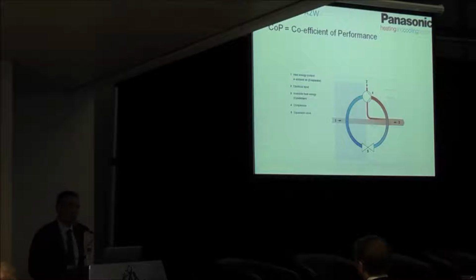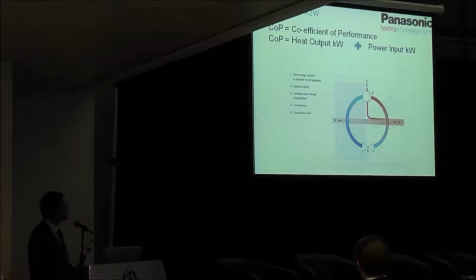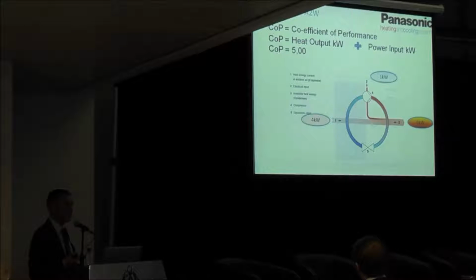So when we talk about air-to-water heat pumps, we hear the term COP, or coefficient of performance, quite a lot. What exactly is that? It's simply the heat output divided by the power input. So if we have a heat output from a heat pump unit of 5 kilowatts and a power input of 1 kilowatt into the compressor, we have a COP of 5. So we're taking 4 kilowatts from the air around the unit. Although that air may be cold, there's still energy and heat in that air, which we can utilise to heat the home.